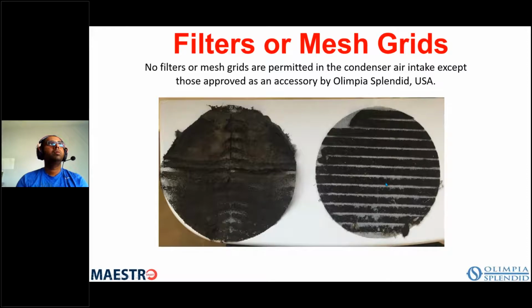The other thing you can't do is just add in any type of filter or mesh, because the result on this job was that the mesh was not maintained by the consumer, and eventually it filled up and blocked the coil, and before you know it, your unit's not functioning anymore. So I'm also working with a manufacturer in China that makes a number of plastic grids, and my goal is to have a grid that I can put in there to keep out geckos and other things. Something that the consumer would have to know is in there and has to be cleaned once a year. And again, hopefully we'll have announcements on that in the near future.